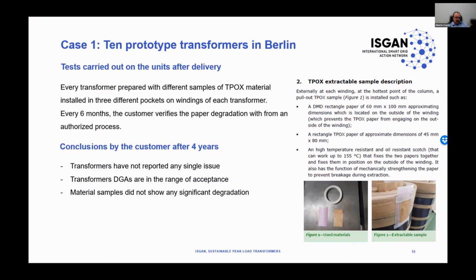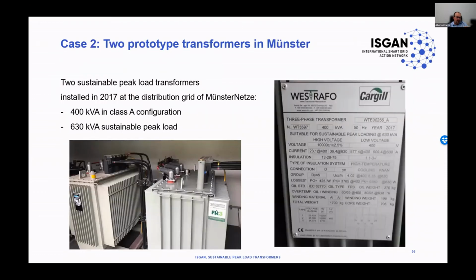We can see another project that we did on the next slide, a second project that is a comparison between a standard 400 kVA transformer delivered by one of our competitors to a German utility company. Next to this transformer, a Westrafo SPL design transformer, with the same footprint and same dimensions, was installed inside the same substation. And as I said before, this is a big opportunity for the utility to reuse the existing substation without doing civil works and having an increase of the power rating available in the substation.